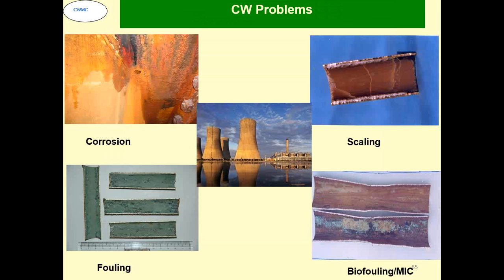Now typically these are the problems which are seen in cooling water: corrosion, scaling, biofouling, fouling. Corrosion is basically an electrochemical reaction involving water and oxygen mostly. Scaling is the precipitation of salts from the system. Fouling can be biological fouling or it can be inert fouling also. Biological fouling is caused by the bacteria or the macro species which are present there. Inert fouling is caused by corrosion products, dust, or the treatment chemicals which are used there.